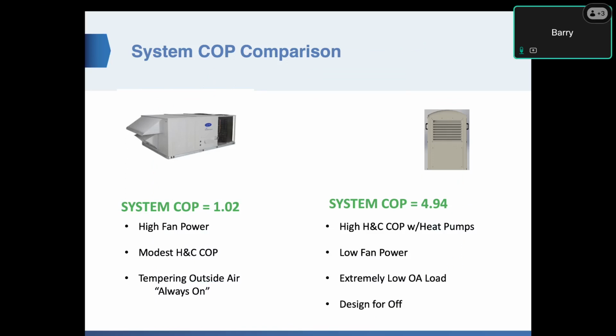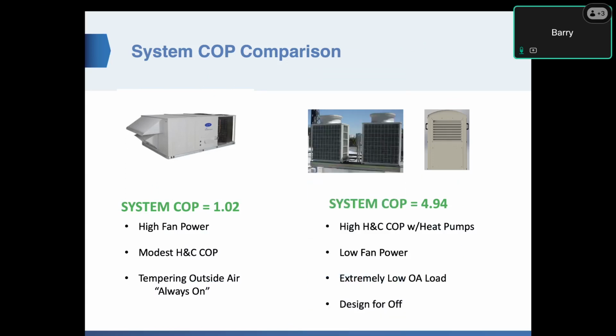To give you a comparison on systems, this is a typical rooftop unit. It's a gas pack rooftop, so it's using gas for heating and it's using DX cooling, electric cooling. And it has a system COP on a year-round basis of about 1. And what you have on the right is using heat pumps and very high efficiency ventilation. As a whole system, you're looking at a COP near 5. So you're using about 20% of the energy for the system on the right as you are on the left. And this has been borne out in many, many projects that we've done where we're saving huge amounts of energy while providing heating, cooling, ventilation for the building.